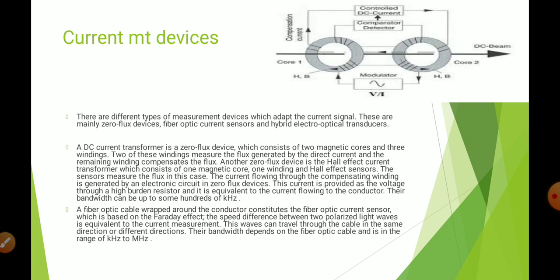A fiber optic cable wrapped around the conductor constitutes the fiber optic current sensor, which is based on the Faraday effect. The speed difference between two polarized light waves is equivalent to the current measurement. These waves can travel through the cable in the same direction or different directions. Their bandwidth depends on the fiber optic cable and is in the range of kilohertz to megahertz.